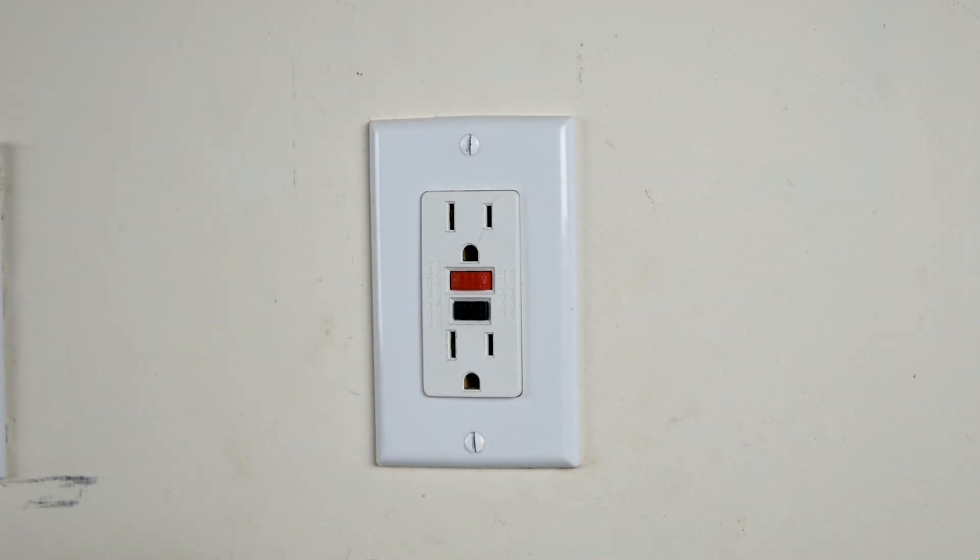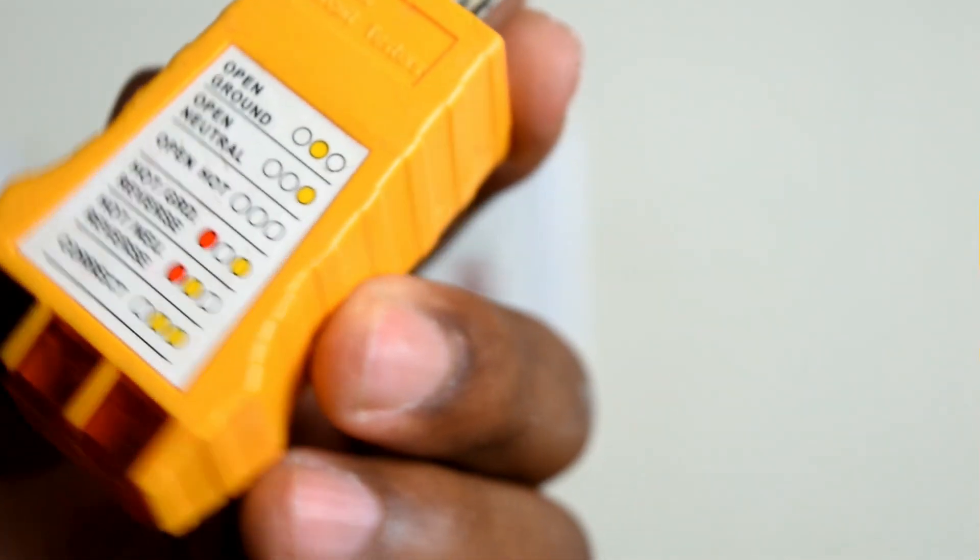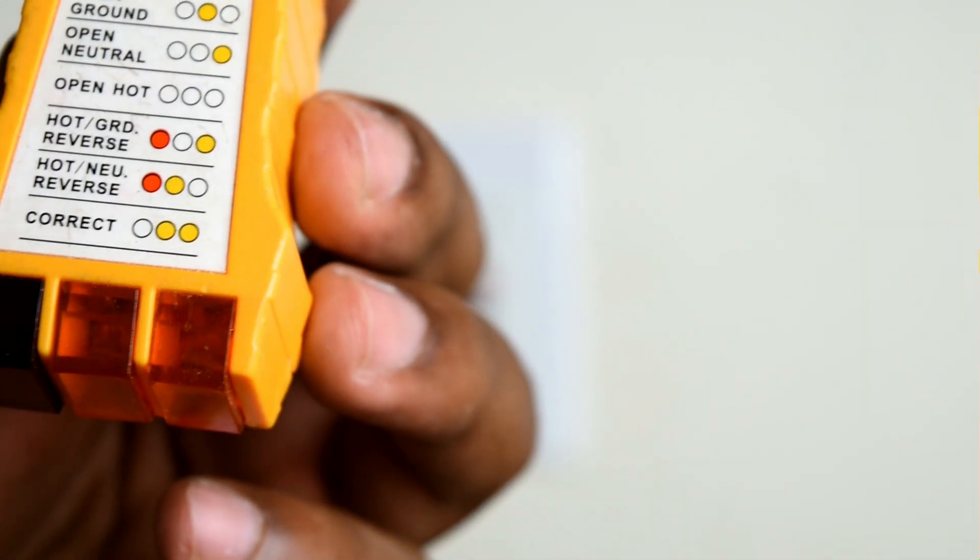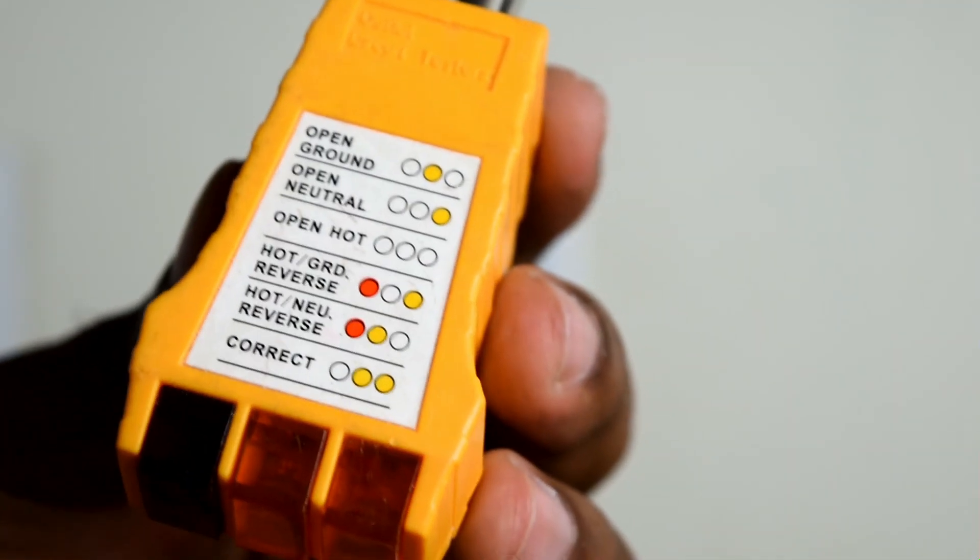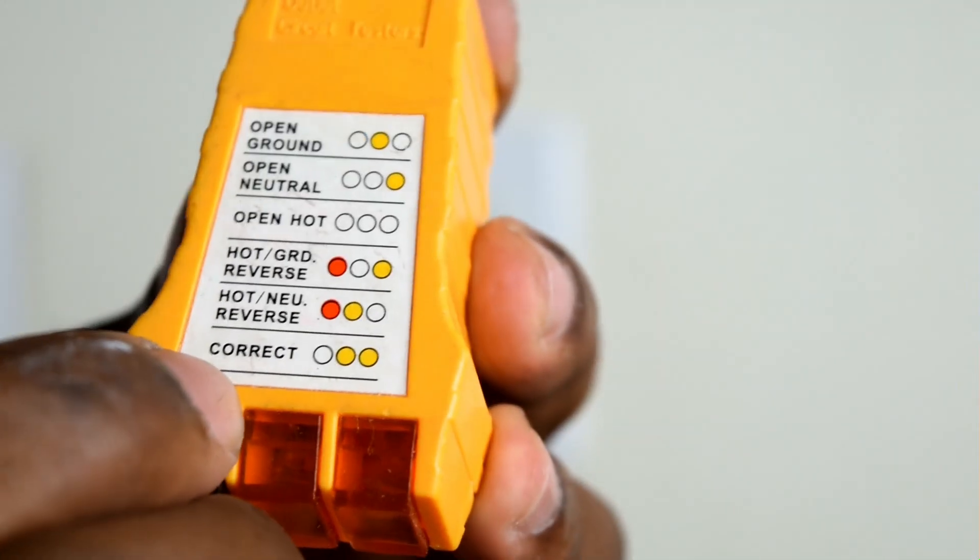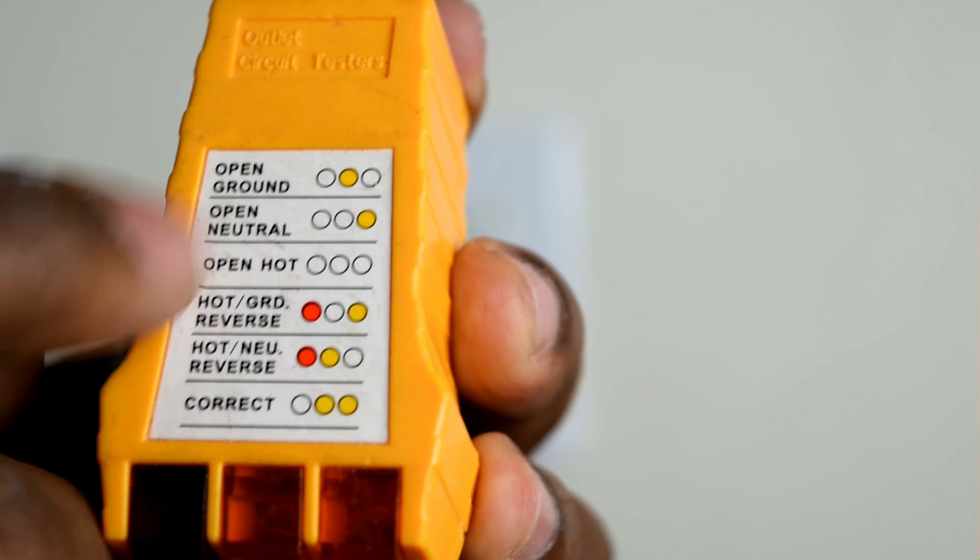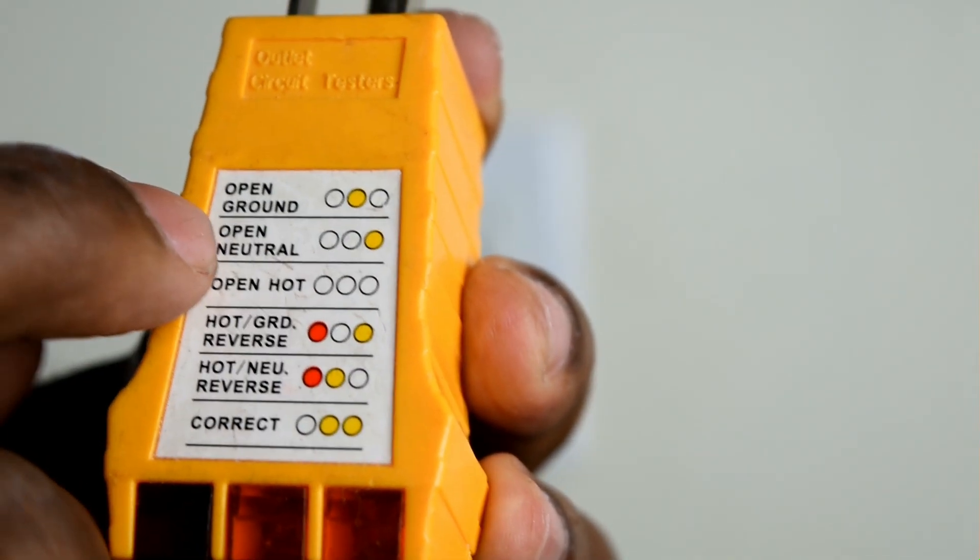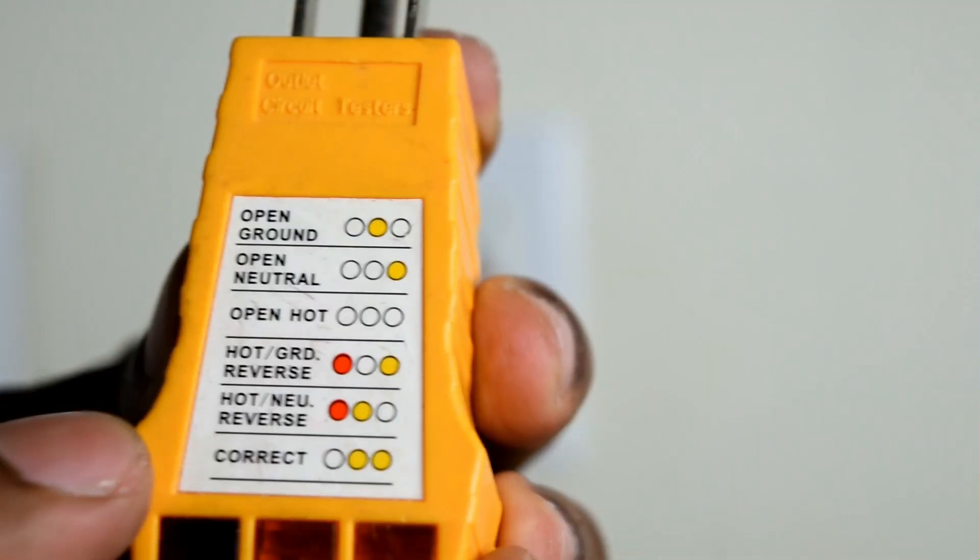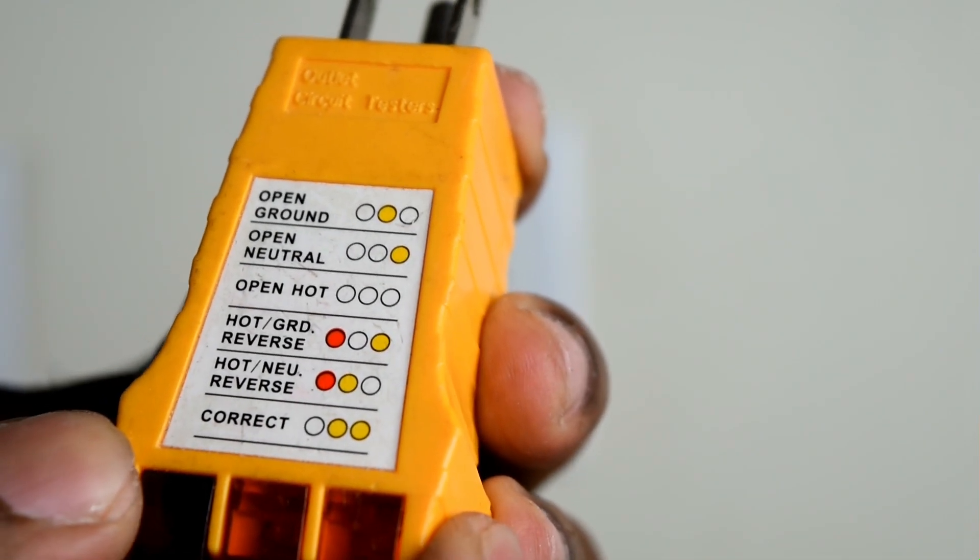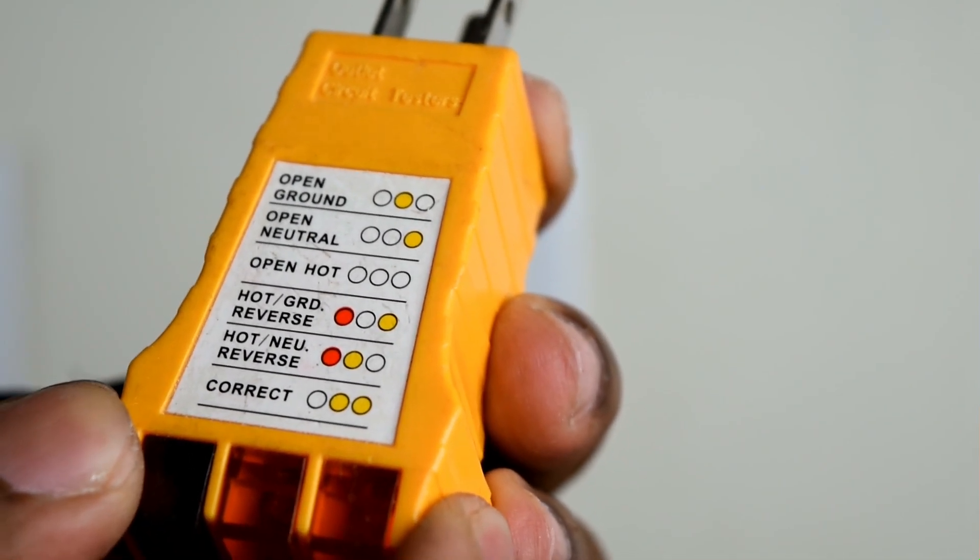So now I'm going to go flip the breakers back on and test this thing. I'm going to use this tool, which is an outlet tester, to basically test my wiring and make sure that it's wired correctly. How this works is you plug this in and it tells you if something goes wrong. Like if you had an open ground, you would see that light come on. All these different settings will tell you if you wired it correctly or not.